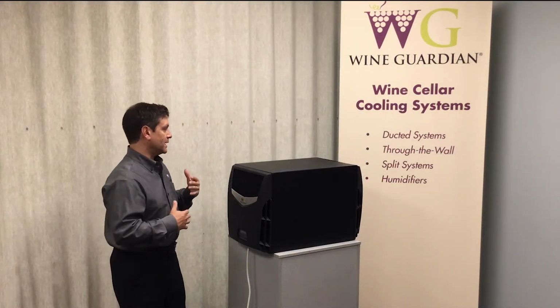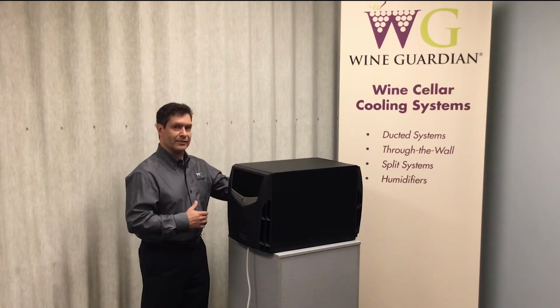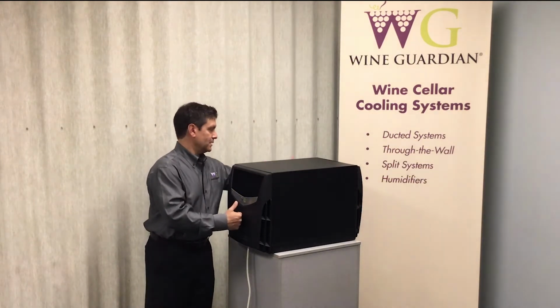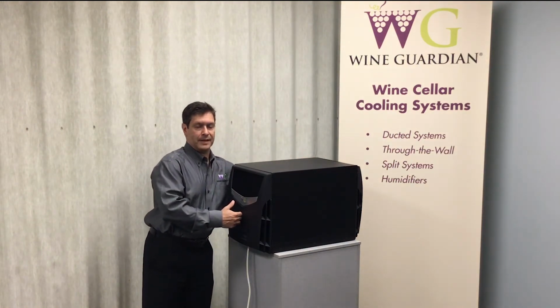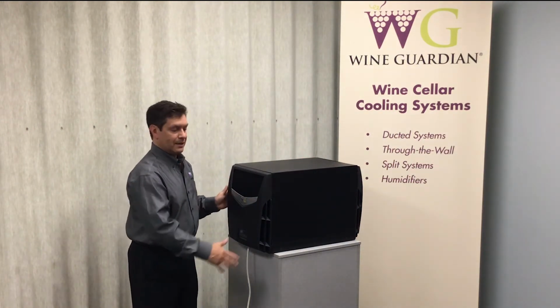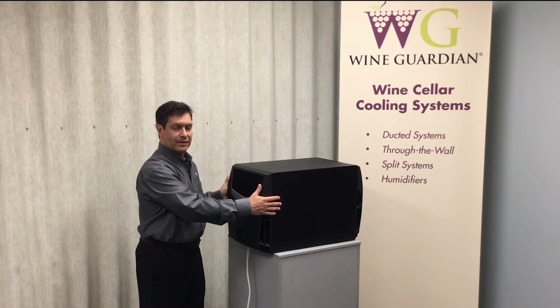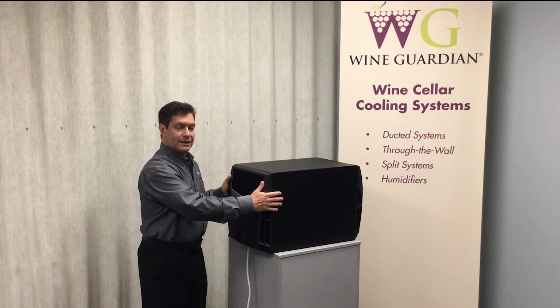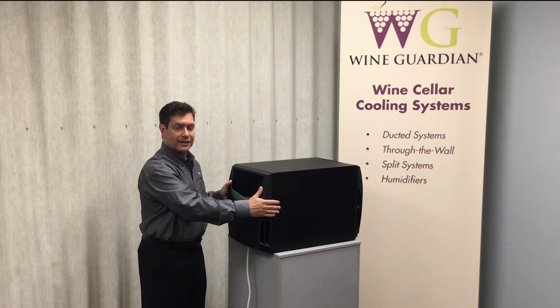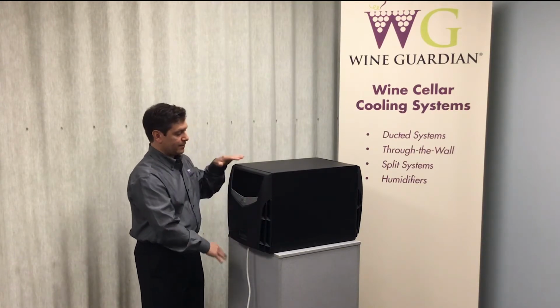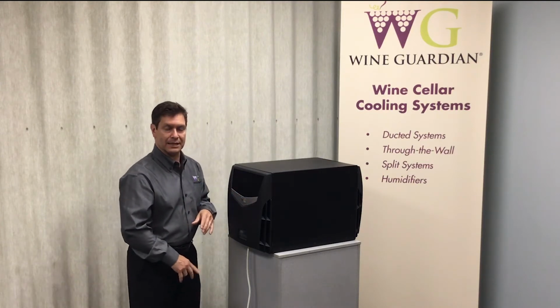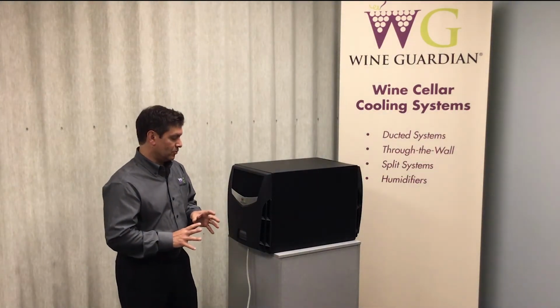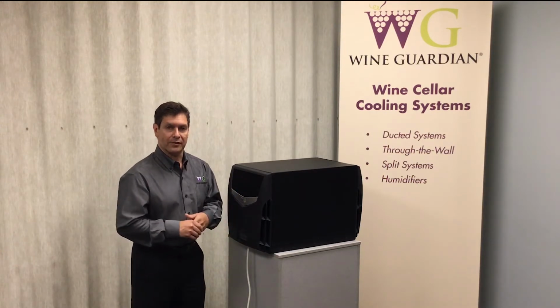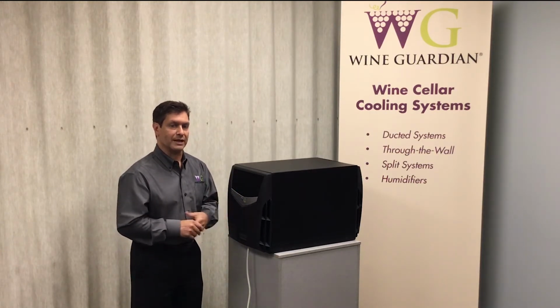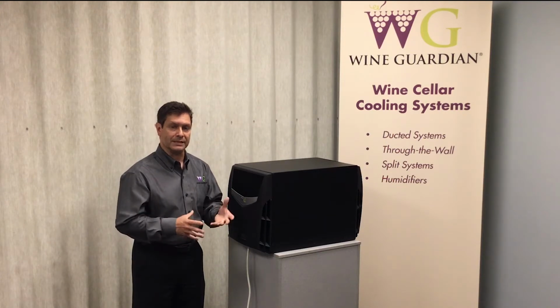Size-wise, the units themselves are exactly 25 inches long from faceplate to faceplate. They're designed to fit within a standard stud width. So this will fit in a 14.5-inch wide opening, and the height is roughly about 16 inches. And we designed it as a replacement for most of our competitors' units, so it should just fit right into the openings that our competitors have if you were to replace one of their systems.